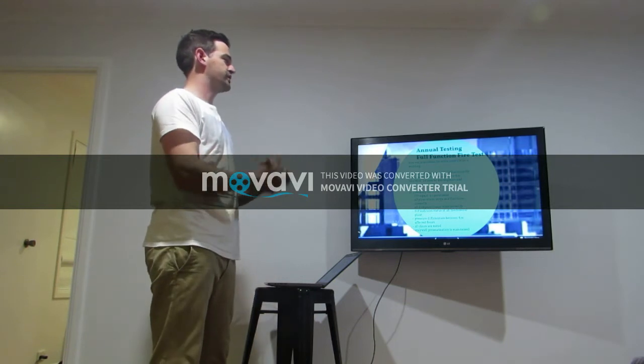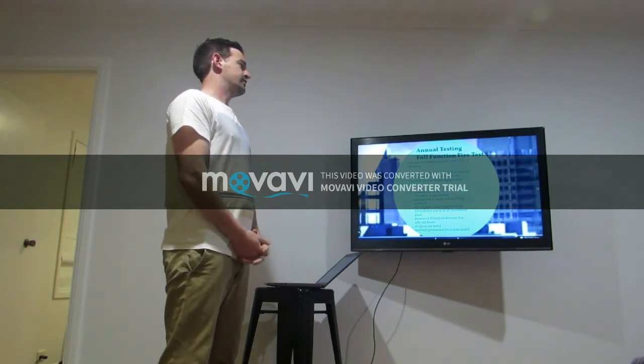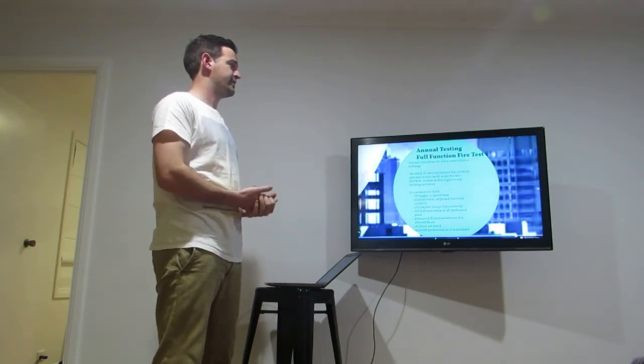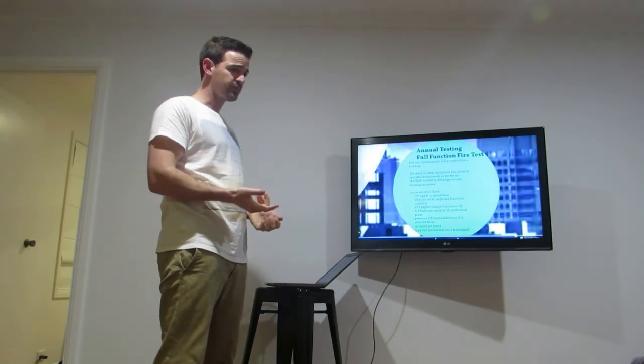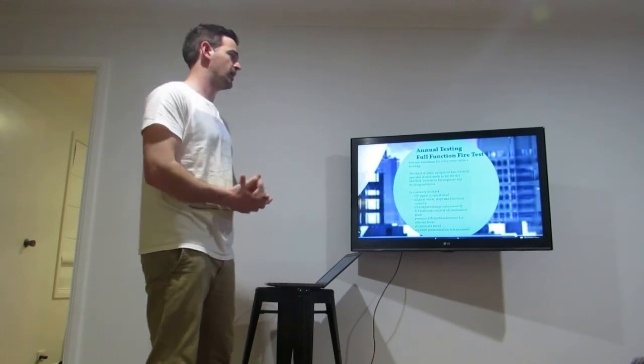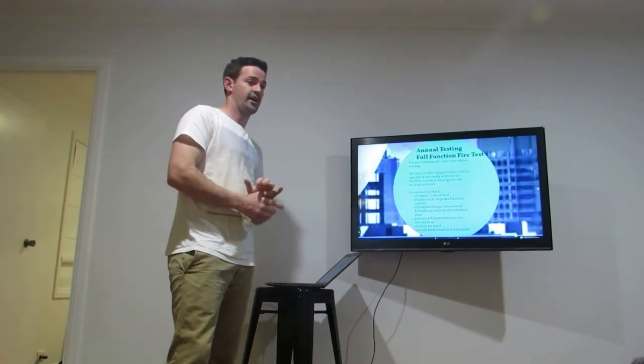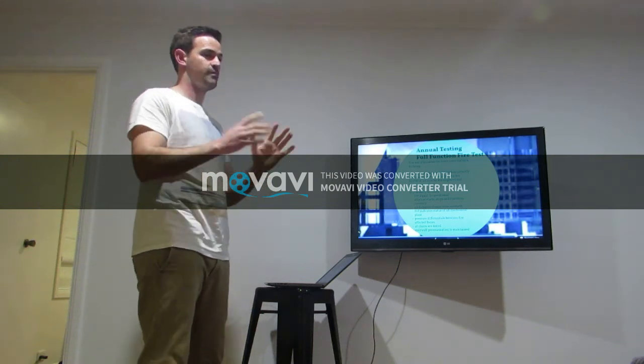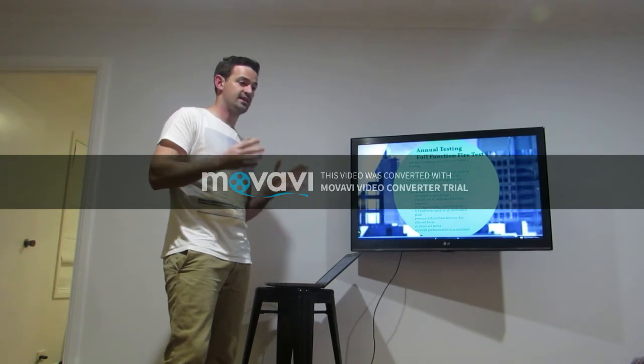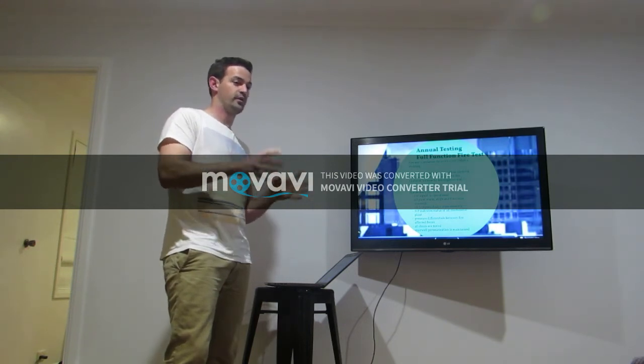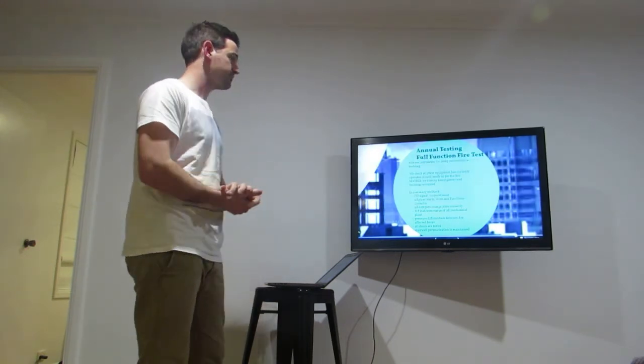Annual fire testing is the biggest. This is the full function fire test. In the annual fire test, every zone within a building is put into alarm. We check all plant equipment has correctly operated in every mode, and we check it against the matrix. The fire matrix is written by fire engineers and building surveyors, and this is exactly how it needs to operate for each specific building.